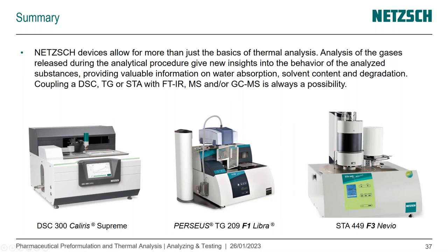It's also possible to have not only one, but two of these gas analyzers coupled to the device. Here in the middle, you see a TG coupled with this small but totally effective infrared spectrometer on the top.